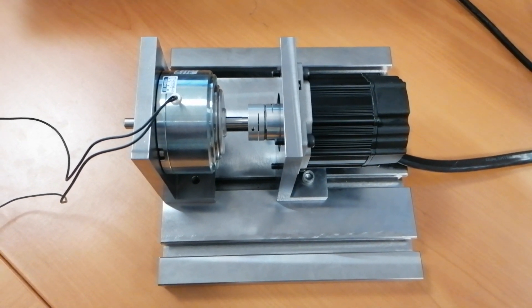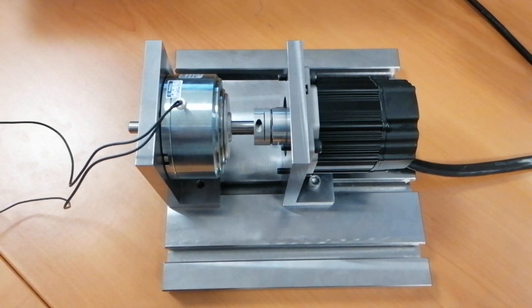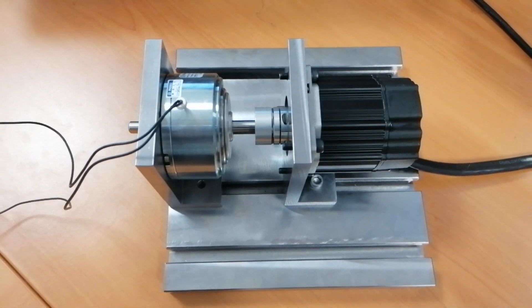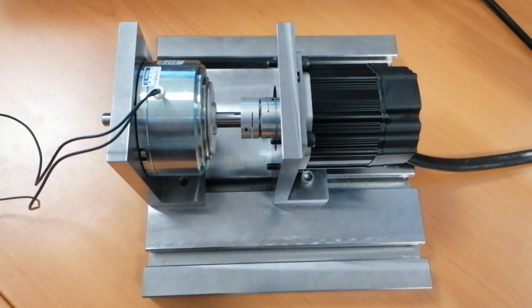The system at 5 rpm. The motor has only one thousand lines of encoder and it has only eight poles, so it's not perfect for lowest speed operations, but as you can see it's smoothly moving at 5 rpm.